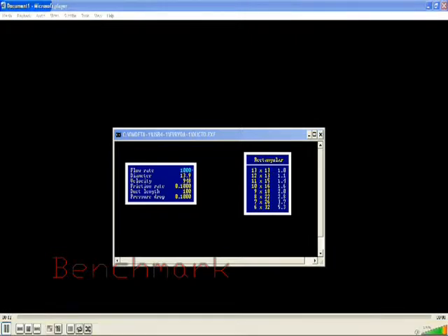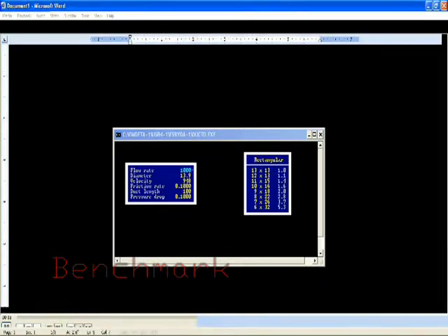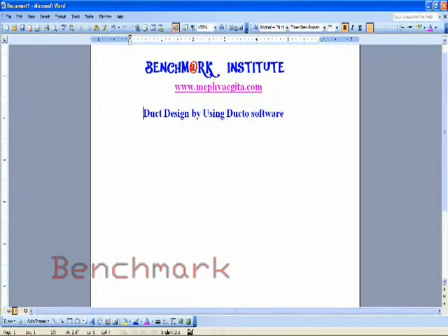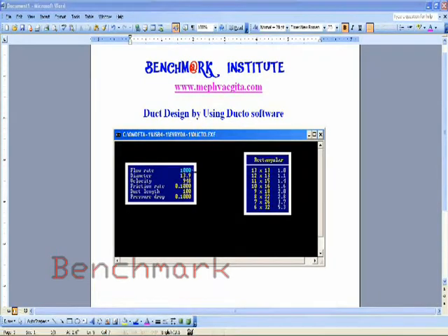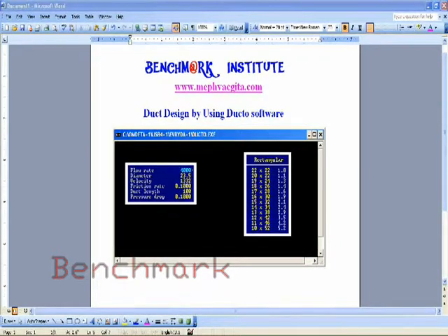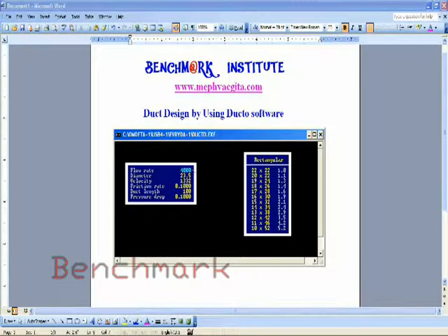In Part 1 we did manual ducting. In Part 2 we are going to use the ducto software for duct design. Using the Ducto software, you just input the flow rate — the CFM air quantity. For serial number 1, that is 4000 CFM, and we are getting 0.1 inch friction with a 30 inch by 16 inch duct size.